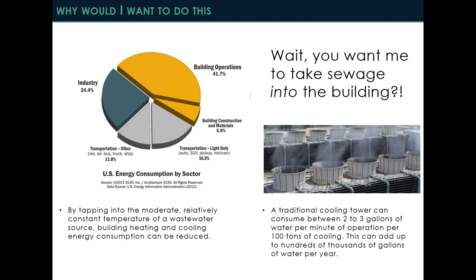Another secondary benefit is on the water side. We tend to be very hyper focused on energy and sometimes forget about net zero water or reducing water usage. One advantage of using sewer heat exchange is that, in lieu of a traditional chilled water system with a water-cooled chiller and cooling tower on the roof, you can use the sewer to replace that cooling tower and reduce your water usage. A traditional tower can use between two and three gallons of water per minute of operation per 100 tons of cooling. For a large office building with hundreds of tons of cooling, over the course of a year it can add up to hundreds of thousands of gallons of water per year.